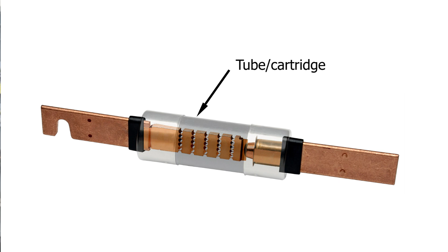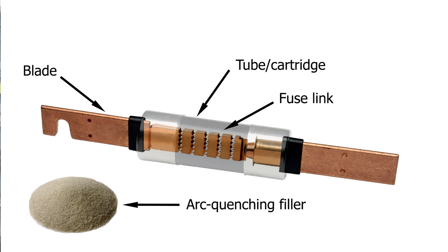The fuse is a highly efficient overcurrent protective device with a simple design based upon principles of physics to interrupt and limit overcurrent events. Fuses have 4 parts common to most designs: the tube or cartridge, terminals, blades or ferrules, the fuse link or element, and arc quenching filler material. Many different sizes and types exist for various applications. The unique construction of the fuse offers several benefits.